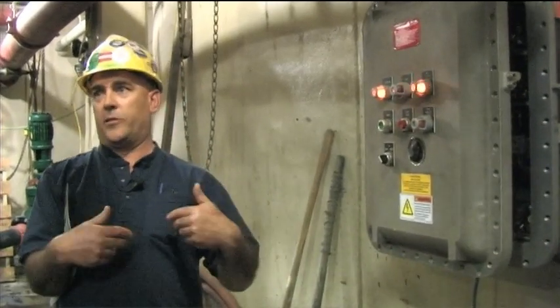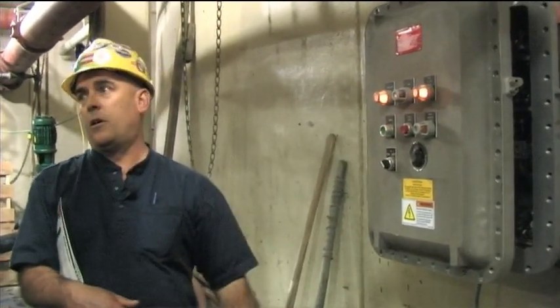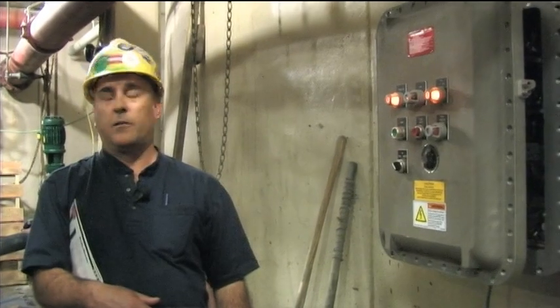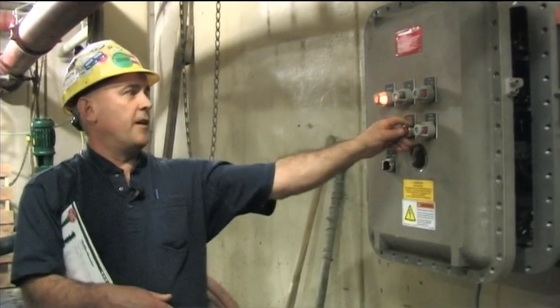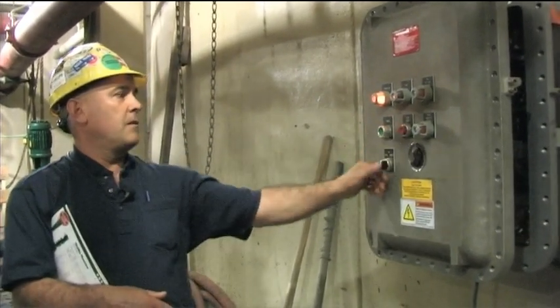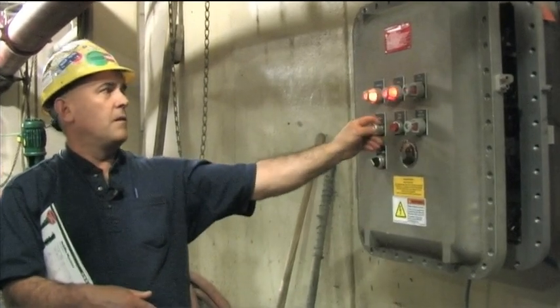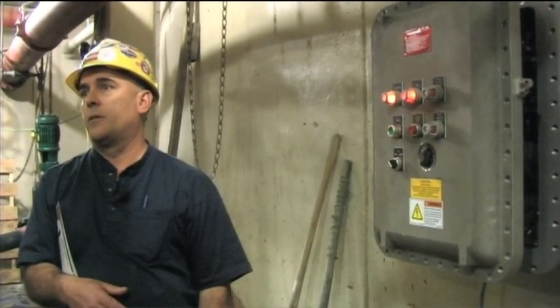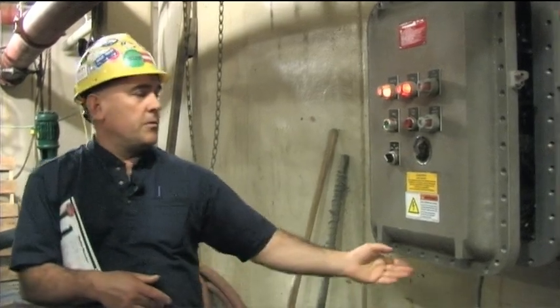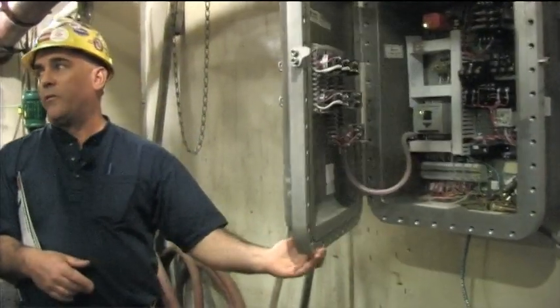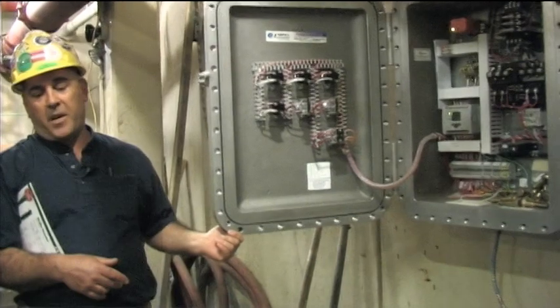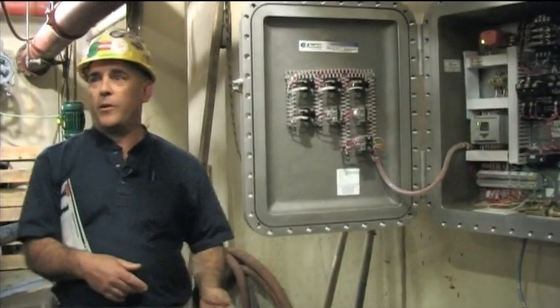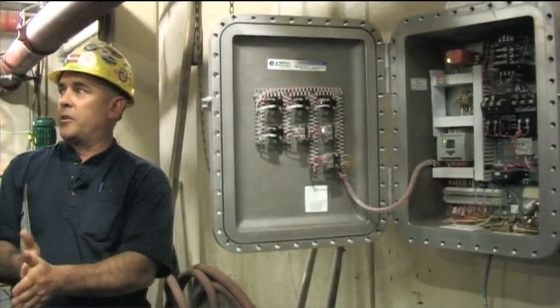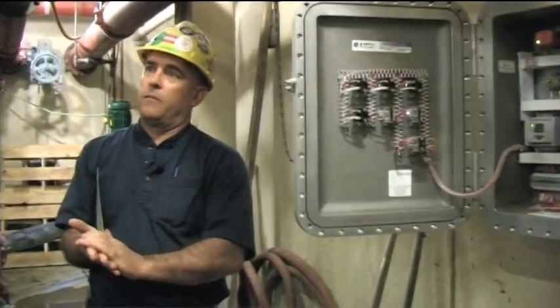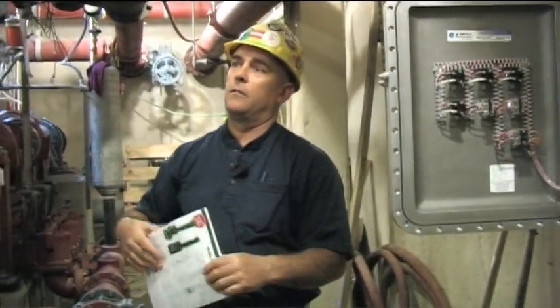That was the contactors, and then you get your fail alarm there. So you just have to reset that, and then you're back in business. So that's pretty much it. I mean, it's pretty straightforward. Again, there's not a lot of maintenance with it, but you know, it needs to be looked at every once in a while just to check the tightness of the cutter stack. And that's pretty much it.